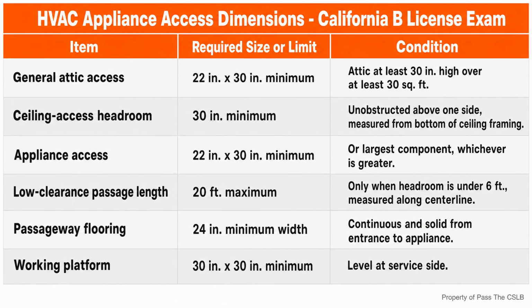Suppose a crew gets a horizontal furnace into an attic before the ceiling is closed. The unit fits between the framing, the ductwork connects, and the job looks nearly finished. Then the access opening is framed afterward as a standard scuttle. Months or years later, the largest service component cannot pass through that opening. The appliance may operate, but the service route was never coordinated. That is the kind of general B problem I want you to catch before finish work hides it.